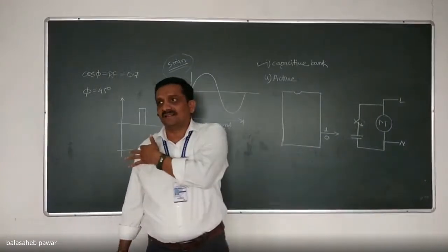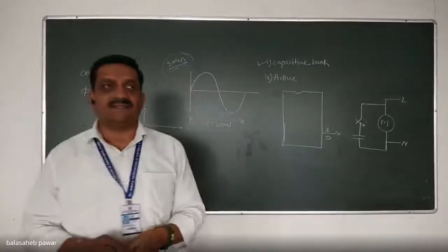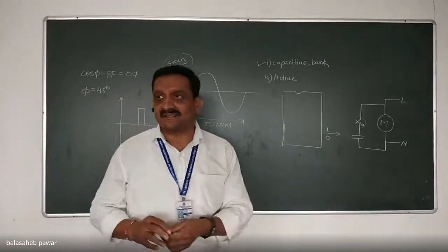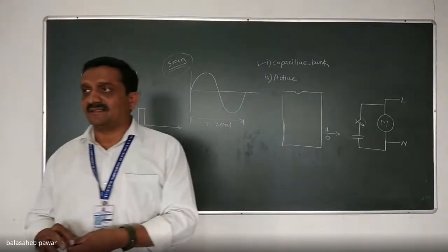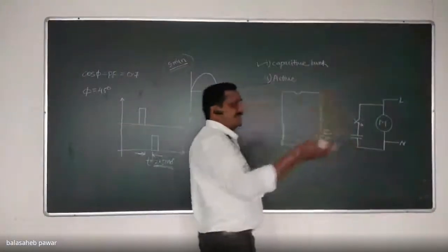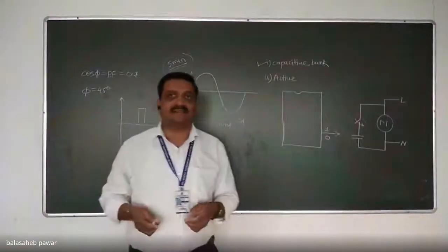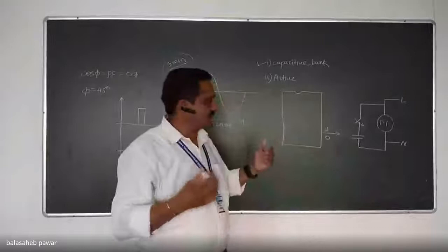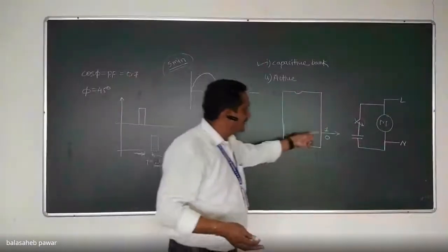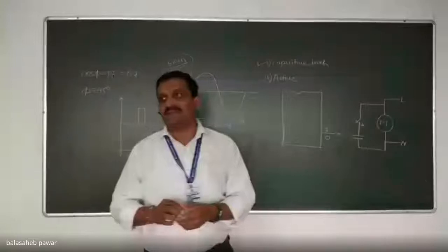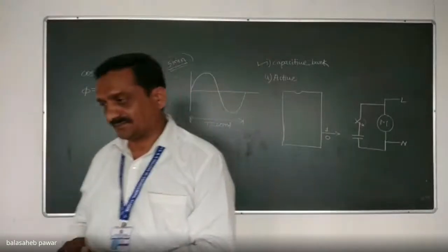Is it clear? Again, as per the given delay of 5 minutes, later on the power factor will again get sensed, will get measured, and if it is above 0.7, then no need to take the action. Again, after the next 5 minutes, the power factor will get sensed and measured. If it goes below 0.7, again action will be taken to generate logic high so that the capacitor will get connected in parallel to the motor. Is it clear now? Is it okay? Yes, sir. Okay.